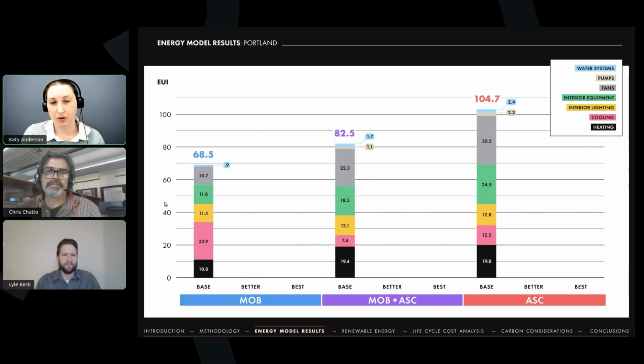This shows the energy results for Portland. I'm doing a deep dive into the Portland results first, and in a little while I'll show the Bend results side by side. This is a detailed breakout of all the baseline results for Portland for the different programs. At the bottom you can see the MOBs in blue, MOB plus the surgery center in purple, and in red at the far right is just the surgery center by itself. This is to get us oriented to the difference in energy use intensity that the program has. You can see the blue MOB starts a little under 70 kBTU per square foot, whereas the surgery center starts at almost 105 - an increase of about 50% compared to the MOB.